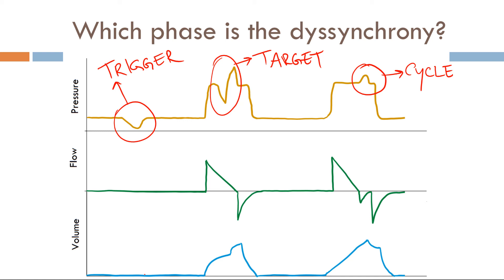Finally, looking at the volume scalar. There's no volume here. Volume increases up to this point. Then you get a small increase in volume up here. Then you get exhalation. Continue along. The volume increases. There's a small loss of volume here, and then a large loss of volume right here.